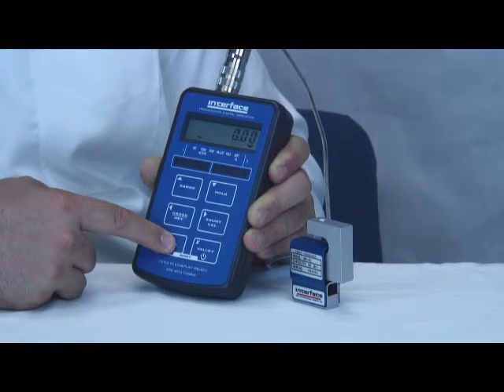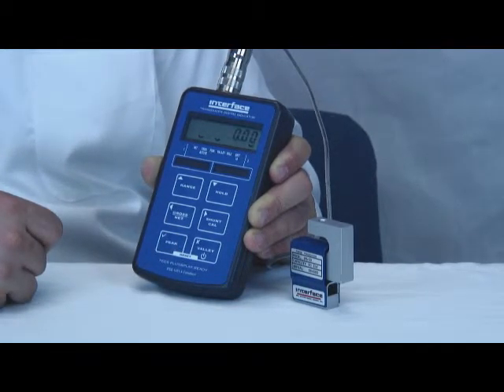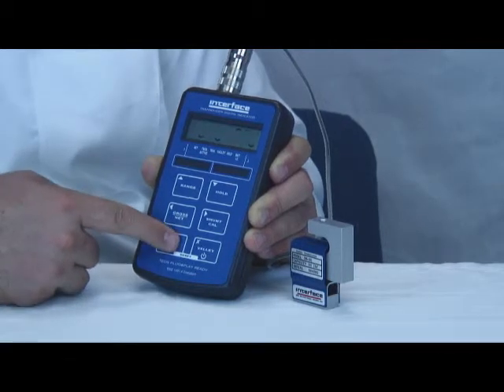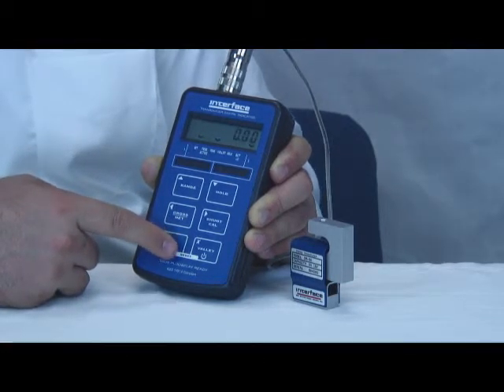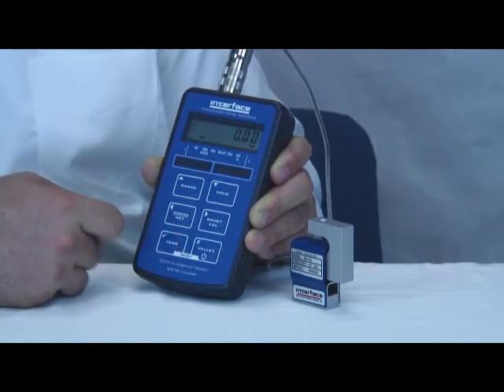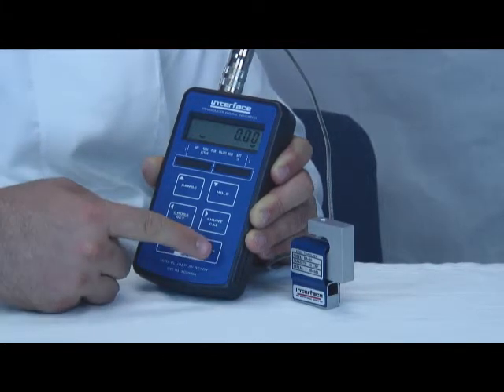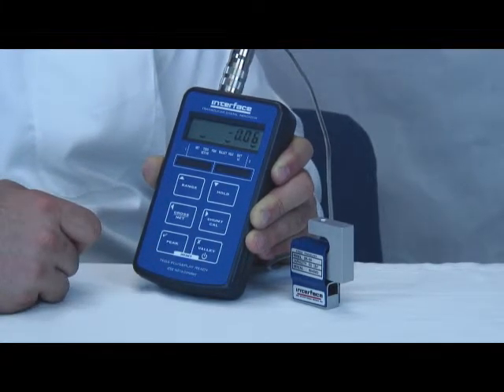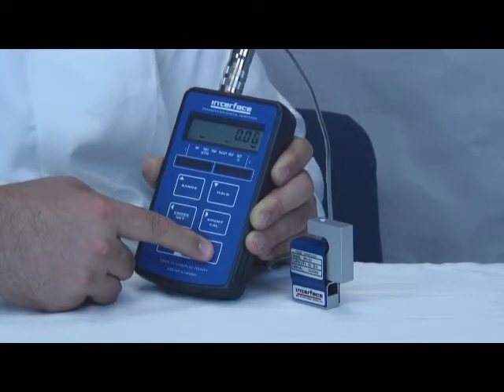displays the peak value, which was last recorded. And you can see the display flashing. That means it's in peak mode. When you press the peak button again, it goes out of peak mode. Same with valley. Look at the low reading, and then when you press the button, it goes back to current reading.